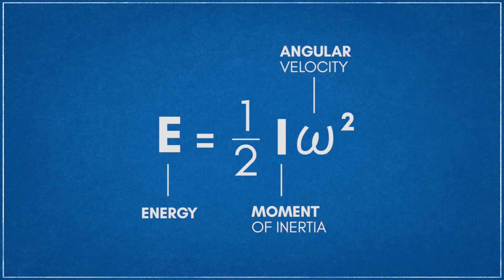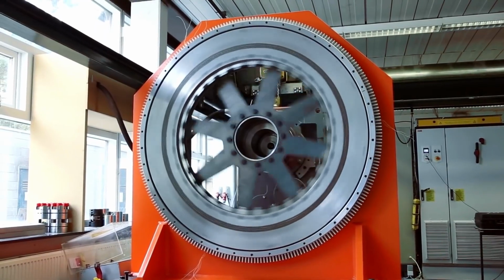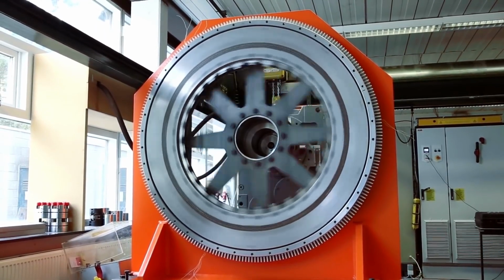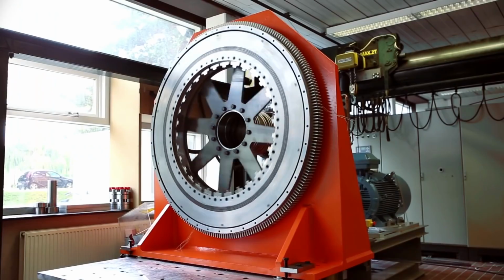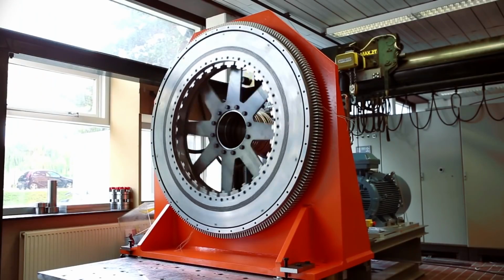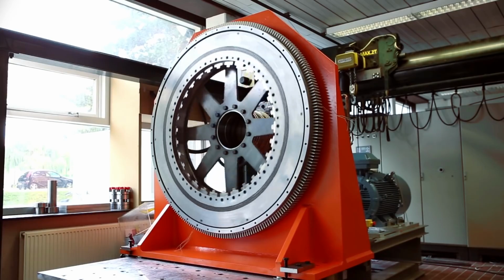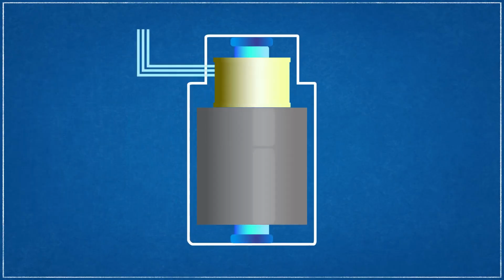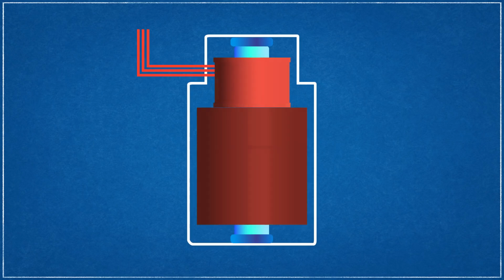In effect, increasing the rotating mass, optimizing the shape, or increasing rotational speed of the rotor allows it to store more energy. In practice, these three properties are constrained by several design factors. The usable rotational speed range of the system is capped by the voltage variation limits of the motor generator system. If the rotor speed drops below a minimum limit, it will produce too low of a voltage when discharging the flywheel rotor, while spinning it too quickly during charging can exceed the torque limits of the motor generator. These limitations of the motor generator system itself will always result in a region of inaccessible storage energy capacity within a flywheel energy storage system.